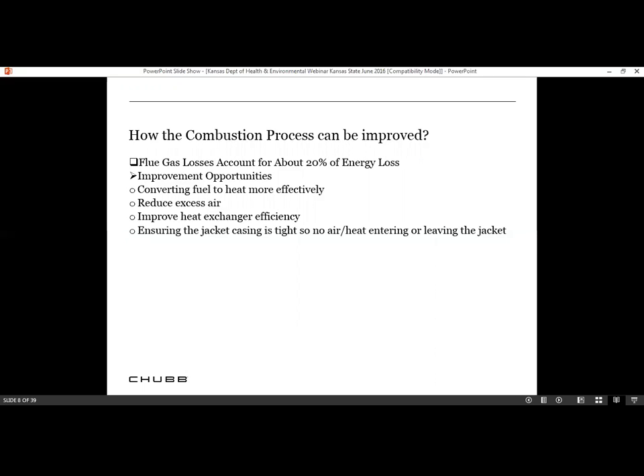How the combustion process can be improved. Flue gas losses account for about 20% of energy loss. Improvement opportunities are converting fuel to heat more effectively, reducing excess air, that's a real key right there, excess air, improving heat exchanger efficiency, and ensuring the jacket casing is tight so no air or heat is entering or leaving the jacket.